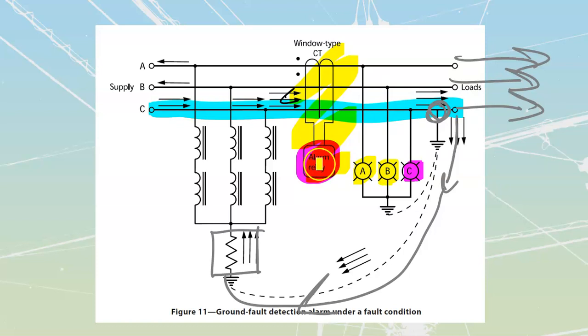I've got an alarm relay that fires on. The C line has gone dark, my A and my B line have gone back to being bright, and the actual current is now being diverted and controlled through this current limiting resistor, or what we would call an impedance that we have across there. This allows us to track down faults really easily because we know exactly which line it is.